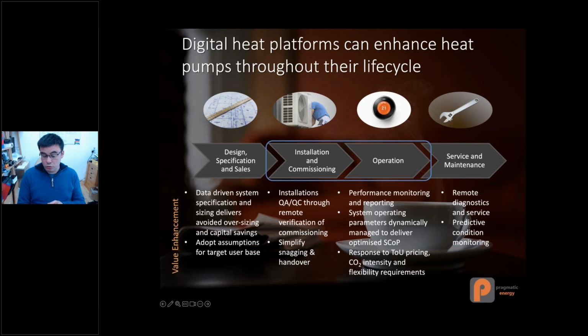No one ever does it, for two reasons. First, it's 250 pages—pretty hard, takes a long time, and you really need to be a controls engineer to fully understand it. Second, the last thing you want is to twiddle with all the default settings and have a customer who doesn't get a warm shower, or is cold, and calls you back. You start off on the wrong foot and end up spending a lot of money snagging issues caused by trying to make the heat pump work as effectively as possible.